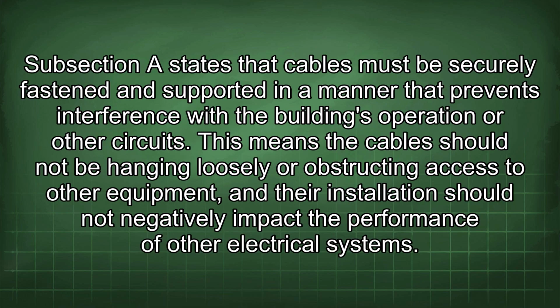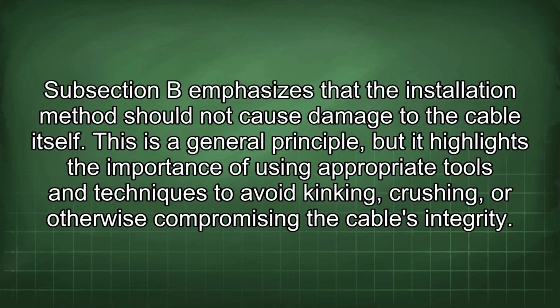Subsection A states that cables must be securely fastened and supported in a manner that prevents interference with the building's operation or other circuits. This means that cables should not be hanging loosely or obstructing access to other equipment, and their installation should not negatively impact the performance of other electrical systems. Subsection B emphasizes that the installation method should not cause damage to the cable itself. This is a general principle, but it highlights the importance of using appropriate tools and techniques to avoid kinking, crushing, or otherwise compromising the cable's integrity.